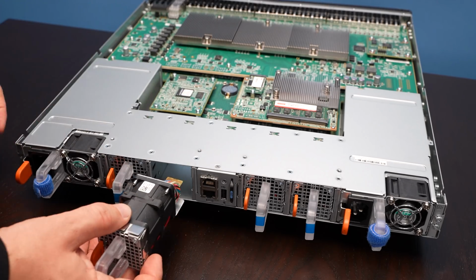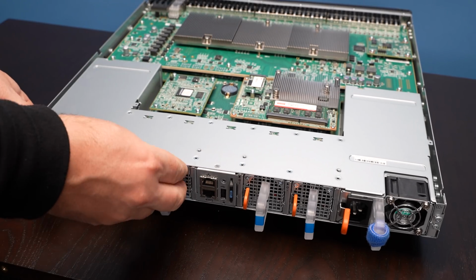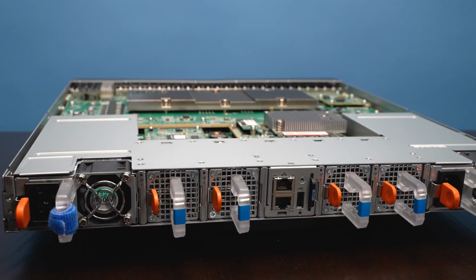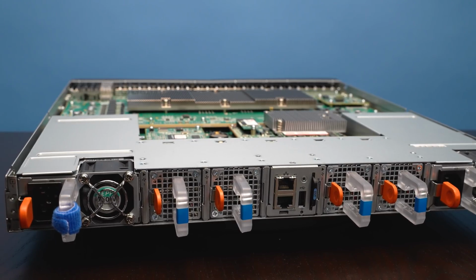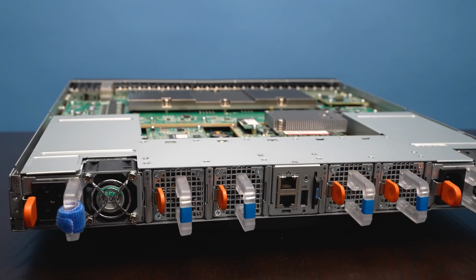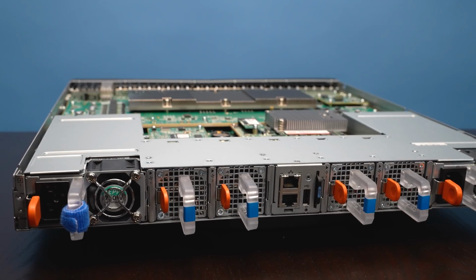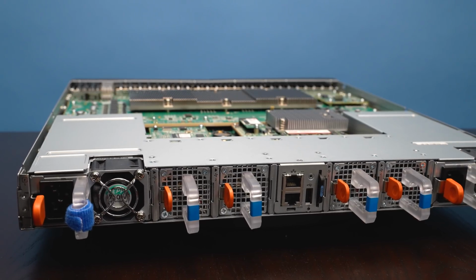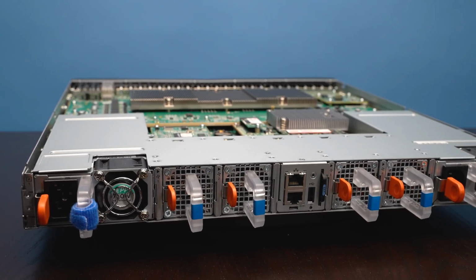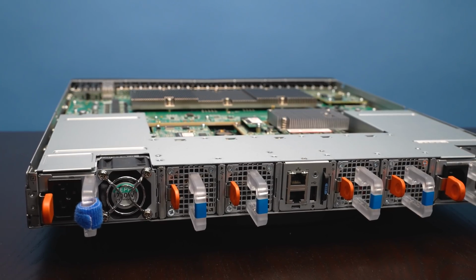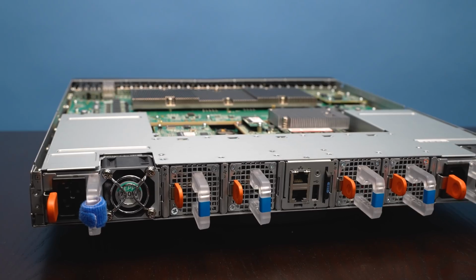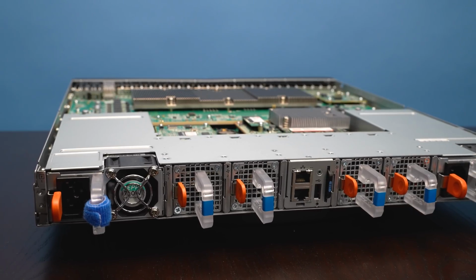You will notice that we do have blue handles on here, and that blue signifies that this is the intake side of this particular switch. Dell has both front to rear and rear to front airflow. What this blue means is that we are taking in cold air through these fans, and then we will exhaust hot air out towards the ports. If these were red, we would have air go in through the port side.